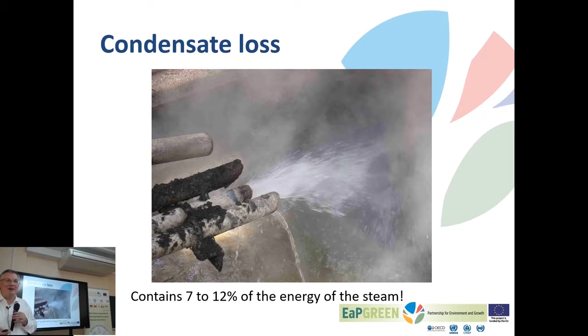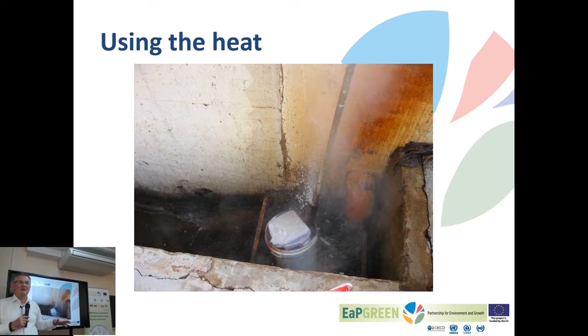The operators had recognized what was the heat content of the condensate which they discharged. This is the same sewer into which we discharged the condensate a few meters downstream. And you see what the operators did? They put a bucket and their lunch boxes to heat the lunch, because they had recognized how much energy there was in the hot water which was discharged. After the condensate had been returned to the boiler, the operators got a microwave to heat their food properly in exchange. Yeah, there are numerous examples.